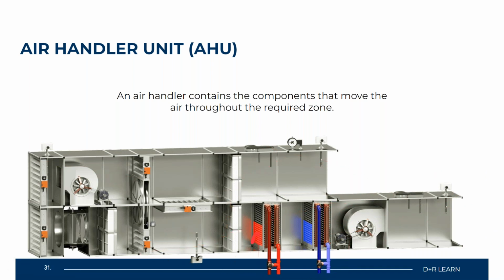So for your air handler systems, I just want you to remember, this is your final destination for the cooling and heating loads which need to be delivered. The heating happens at the heat exchanger, and the cooling happens at the cooling coil. Two separate coils. It's not going to happen within the same coil. From there, you will have your heating and cooling happen, and any return air is drawn back out by a motor system to the ambient space. Then that operation continuously happens within your system as long as there is a call for it.